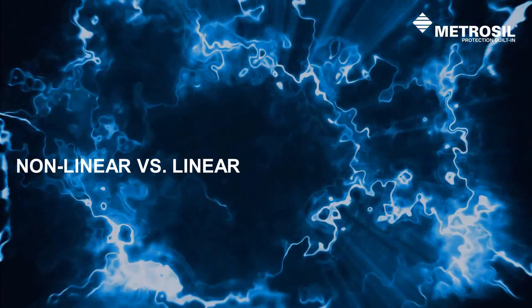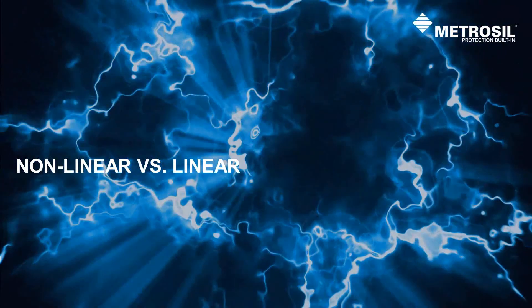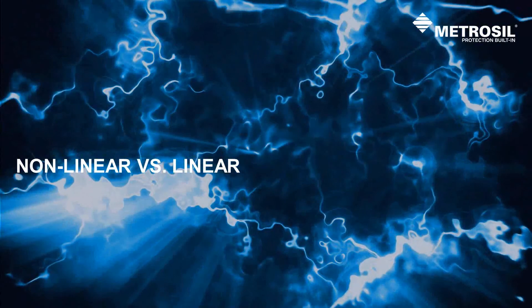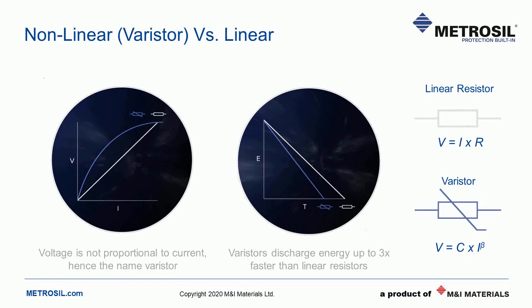Most of you are probably familiar with resistance and Ohm's law — V equals IR. In most cases R is a fixed quantity that expresses the relationship between current flow and voltage. For a linear resistor, double the current and the voltage doubles as well. With a Metrosil, Ohm's law doesn't apply and we don't have a fixed resistance. Instead, we follow a power law: V equals C times I to the power of beta, where C and beta are characteristic parameters of the Metrosil. The effect is that when you double the current, the voltage doesn't double — it only raises slightly. For a relay Metrosil, you would need more than 10 times the current to double the voltage across it. Most overvoltages are transient events with finite energy and simply dissipate this energy into the Metrosil long before such high currents can be achieved.